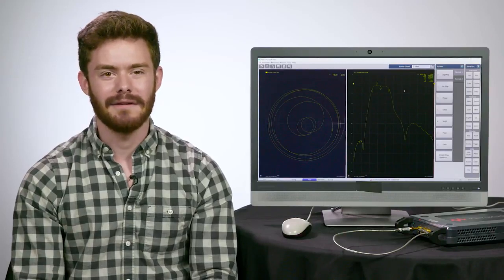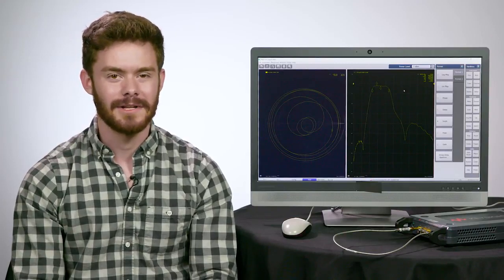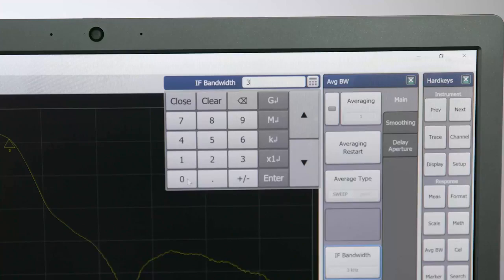The wider the IF bandwidth is set, the faster the measurements can be performed. So let's set the IF bandwidth to 300 kHz by going to Average Bandwidth, IF bandwidth, and enter that frequency.